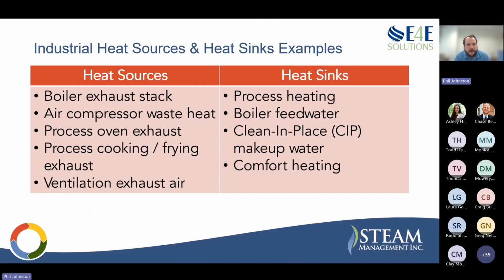So the first thing you have to do when looking at this is really understanding what the sources and sinks are at your facility. I've thrown up some examples here. This is not an exhaustive list for sure, but these are some examples of heat sources and heat sinks. In general, from the source side, it's a lot of waste heat. Whether you have a process that has some form of gas firing or heating that has an exhaust stack to it, that's certainly a good source of heat. You also have standard industrial equipment like boilers and air compressors that give off heat as well. So those are things to find on the source side.